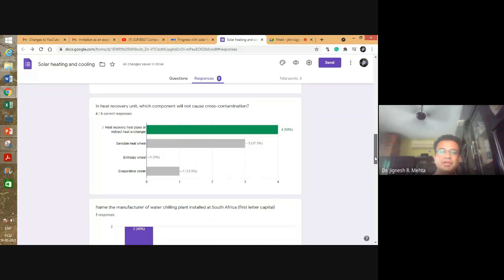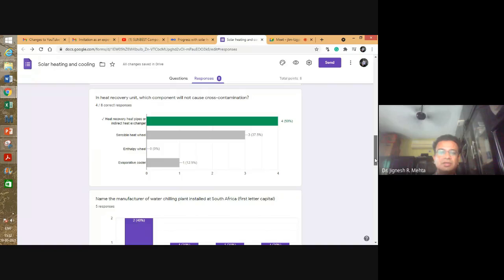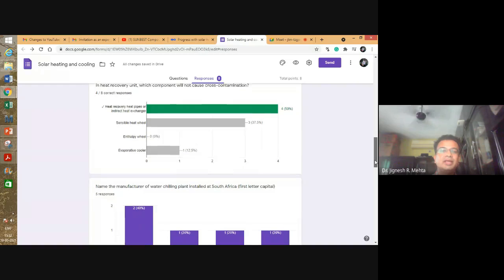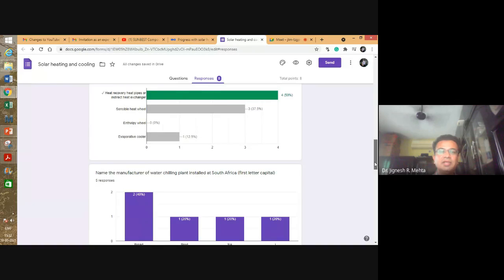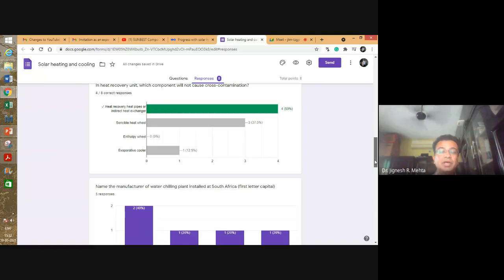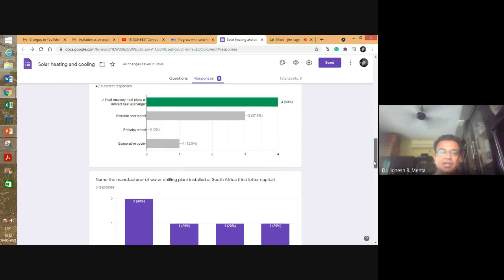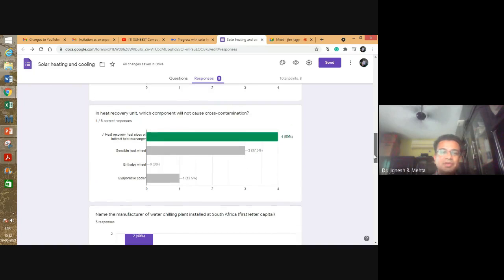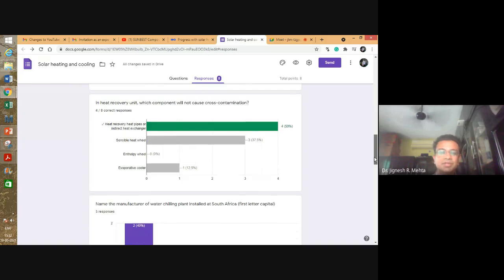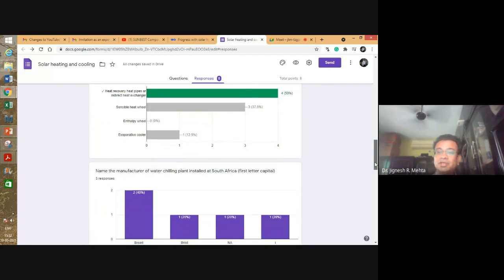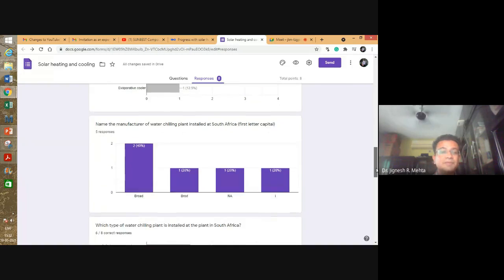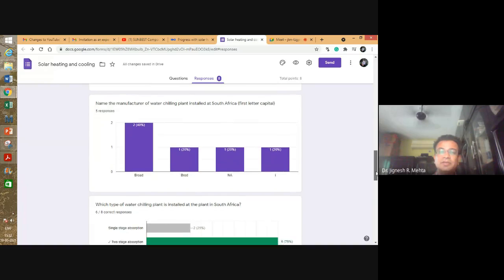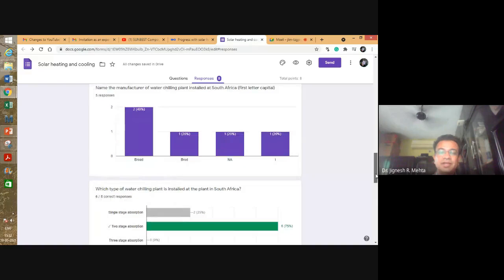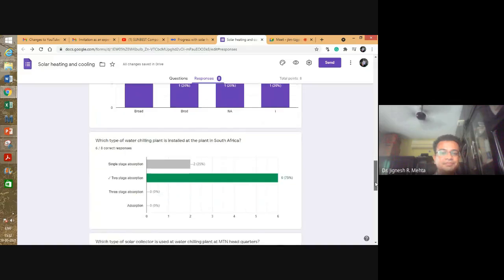And for heat recovery units, which component will not cause cross contamination? If you use an indirect heat exchanger or heat pipe, it will not create cross contamination between the outdoor air and the exhaust air. But if you use a sensible heat wheel and enthalpy wheel, it will. Of course, evaporative cooler will also not create cross contamination. Yeah. So when you make a quiz in a hurry, you also make mistakes. Name the manufacturer of the water chilling plant. Yes, it was Broad. It could be read in the video.